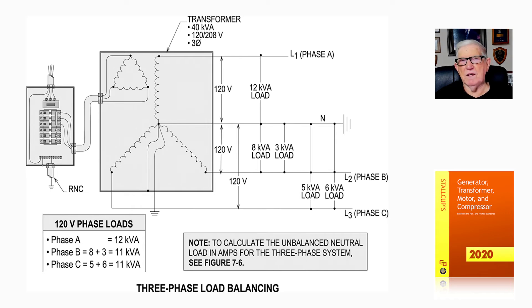So when you add those together, that's how we come up with 120-volt phase loads right below the transformer there: phase A is 12, then B is 8 plus 3 to give you 11, and C again, 5 plus 6 is 11.